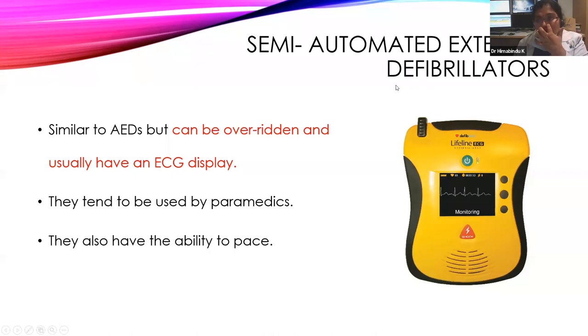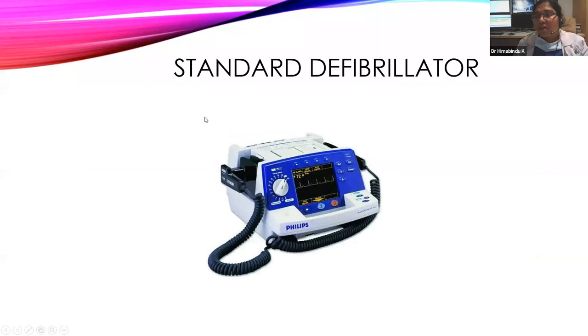The semi-automated external defibrillator is similar to the AED but can be overridden and usually has an ECG display — the paramedic can change energy or decide whether to shock. The standard defibrillator has two paddles, energy selection, charge button, shock button, and a synchronization option for cardioversion. There is also the implantable cardioverter-defibrillator (ICD), placed within the chest with leads in the atrium and ventricle for pacing plus defibrillation.